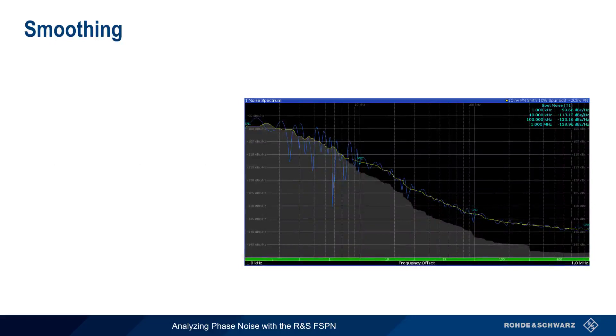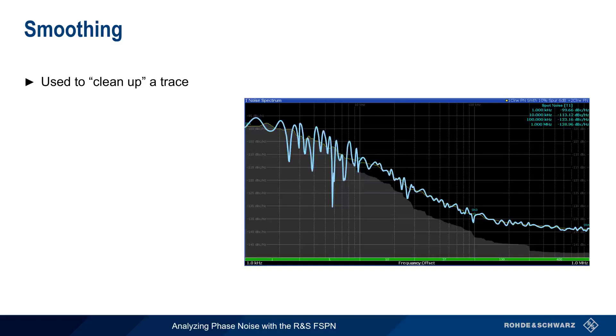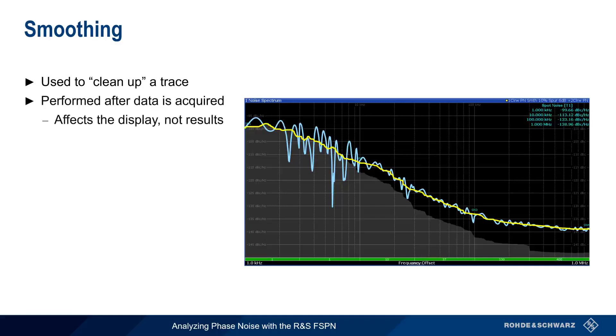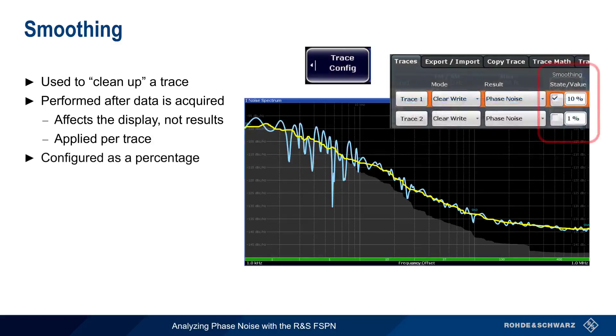Now that we've covered the important noise configuration parameters, let's spend a minute talking about ways of displaying phase noise results. Smoothing is used to clean up traces. Here is the raw or unsmoothed trace, and here is the smooth trace. Smoothing is performed after data is acquired — that is, it affects the display, not the results. Smoothing is also applied per trace, and it's possible to display both the smoothed and unsmoothed traces simultaneously, as shown here. Smoothing is configured using Trace Config and is specified as a percentage. Larger values increase the smoothness of a trace.